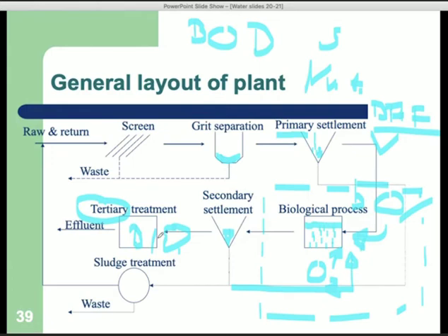From a size point of view, it is much cheaper to build one large tank than two small tanks. That's always more cost effective in any process engineering. A bigger thing is always cheaper to build than smaller things if the smaller things together have the same volume. But the reason for having a second biological treatment system would be that of selectivity. The bacteria are competing like anything out there in the wild, so the strongest and the fittest survive.